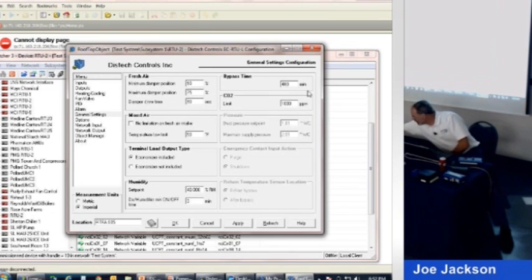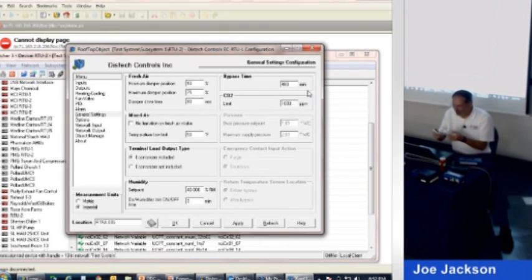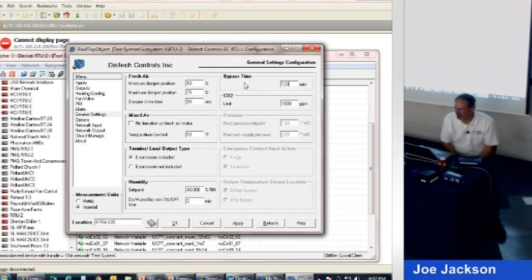We picked the thermostat with an override button. The override button actually shorts out the temperature sensor. That's all it does. But when this controller sees its temperature sensor gets shorted for 3 seconds, it says, oh, somebody pushed the button. And if it was in the unoccupied mode, generally I'd set that for 120 minutes, the unit would come back on and run in the occupied mode for 2 hours, or whatever you set that at.